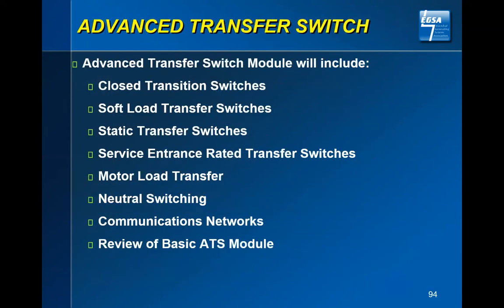To close out the advanced transfer switch, we'll do a little bit more of a deep dive into the closed transfer switch. The soft load transfer switch we've sort of touched on. A static transfer switch is SCR driven, silicon controlled rectifiers. Those will typically transfer within a quarter of a cycle. ASCO no longer manufactures this. That product was spun off when we were sold to Schneider, and the Liebert people offer this transfer switch. Typically, they are in association with UPSs, but it is referred to as a static transfer switch.